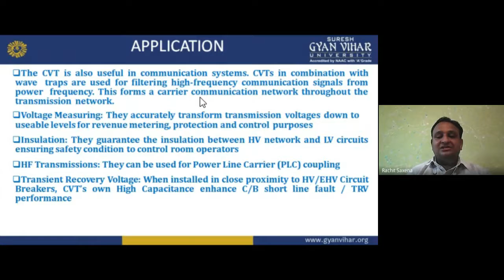Now, the difference between CT, CVT and PT. What are the differences we have? A CVT is the capacitive voltage transformer consisting of a stack of series connected capacitors; the voltage across the capacitor is used to measure the voltage. It also serves the purpose of power line carrier communication. A potential transformer is an inductive step down transformer used for measurement of voltage and protection. But the CVT is used for voltage measurement and for power line carrier communication. A CVT is rated for extremely high voltage, above 230 kilovolt. So we can use it for 400 kilovolt, 765 kilovolt. But PTs are not designed for such large voltage, only up to 12 kilovolt. So for 11 kilovolt we can use a PT, but for more than that we can use a CVT, for high voltage.